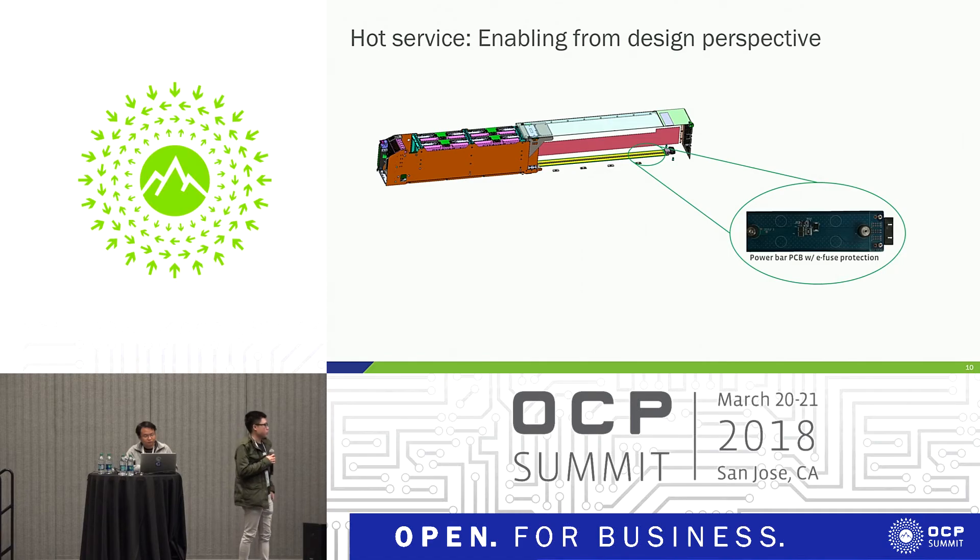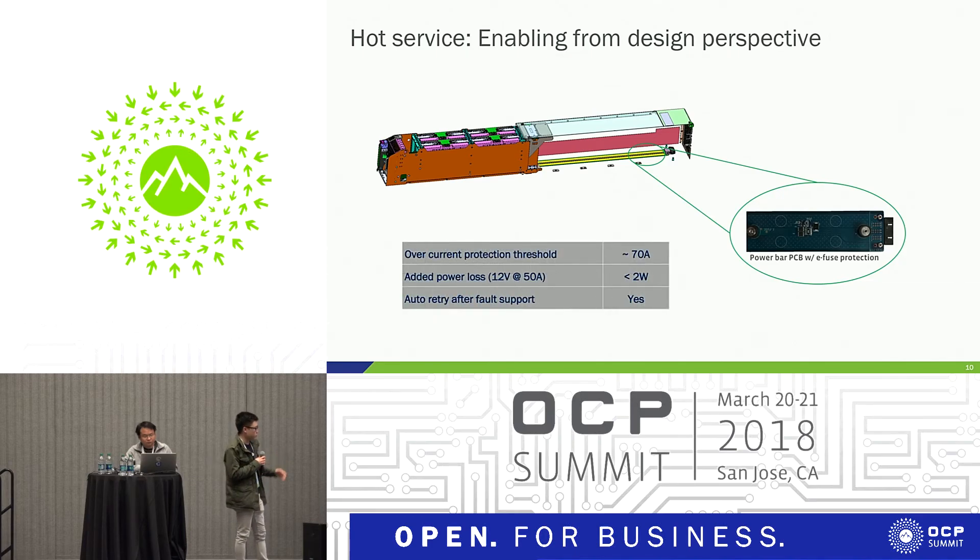On our power PCB, it's essentially just a power connector, but the one thing we added was an e-fuse for protection. It operates standalone. Some quick notes: overcurrent protection is aimed at around 70 amps; total added power loss is less than 2 watts during 12V @ 50A; and it automatically retries after a fault. This works seamlessly without the data center technician needing to figure out if something is wrong with the power bar.